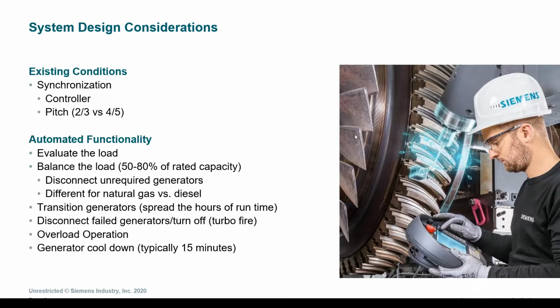Additionally, on that overload operation, generators are built with the capability of temporarily being overloaded, but as soon as that limit is reached, that load gets shed, and we'll get into that more in a few minutes. And then finally, when the transfer switches go back to the normal source, the generators go into the cooldown automatically, which is typically 15 minutes, but again, this is pre-programmed into the functionality of the generators.